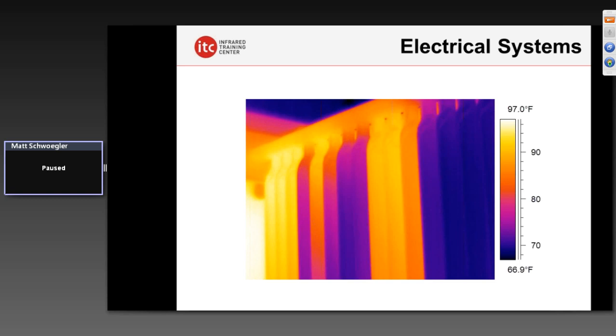It's not always energized components. We also have fluid systems — from a mechanical perspective, these are the oil fins on a transformer showing us variations in temperature. The cooler tubes represent areas where oil isn't flowing, perhaps due to a blockage or low oil level. This heat exchange system isn't functioning as well as it could, and we're seeing an example where cold is actually the problem — it's not always hot that we're looking for. These thermal patterns representing issues could be cool patterns as well.